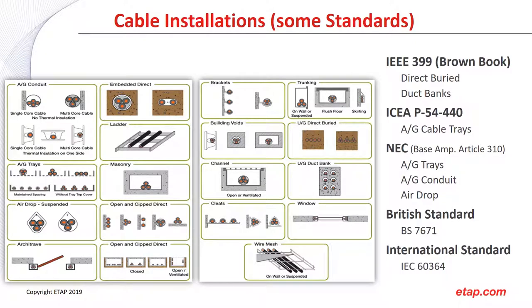We've had a chance to go over some of these installations. The standards used around the world include: IEEE 399 brown book, which covers direct buried and duct banks; ICEA P54-440, commonly used for above-ground cable trays; the National Electric Code (NEC), which provides installation tables for above-ground trays, conduits, and air drop. For IEC users there is the British Standard BS 7671 and the international standard IEC 60364.